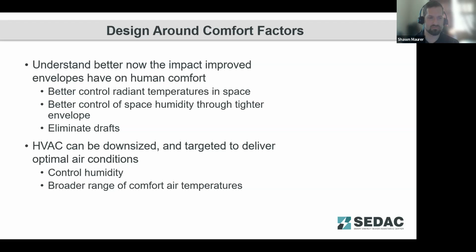You also have better control of space humidity, which again impacts your HVAC sizing. If you've got humidity coming into the building, getting pulled back into the return of the system, that's an additional latent load that system has to then manage. If you seal that up tight and you control that ventilation air through a dedicated ventilation system or your central air conditioning system, you've got much better control over that ventilation air. And you eliminate drafts that create uncomfortable conditions for the occupants. Again, particularly noting in the wintertime, people sitting next to windows or exterior walls can feel that convective draft off those cooler surfaces that leads to a lot of building comfort complaints.